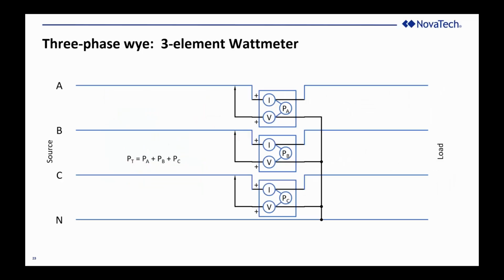So the first step of increasing complexity from the single-phase wattmeter is essentially the Y-connected three-phase line, on which the total power can be measured with a three-element wattmeter. So a three-element wattmeter simply passes the current. Now, let me take a step back. I am deliberately not showing the CTs and the PTs where they would normally be in a substation. I'm simply showing the current and the voltage. If you can imagine the conductors that I'm showing for A, B, C, and neutral as being the secondary side of CTs and PTs in all cases, it eliminates a lot of complexity in the drawing, and it just makes it easier to focus on the concept.